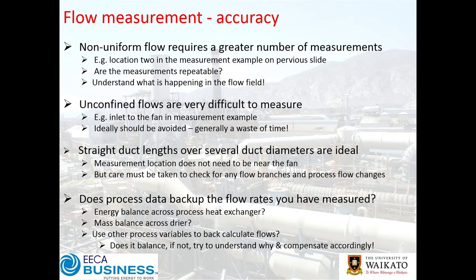Better to get a decent measurement in a contained duct, several duct diameters away from obstructions and corners. Be careful of flow branches and process flow changes in relation to where your measurement is taken. Also look for process data backup: does your measured flow rate ring true in terms of a mass and energy balance? Across a heat exchanger, a dryer — what other process variables can you use to verify your measurements are reasonable?